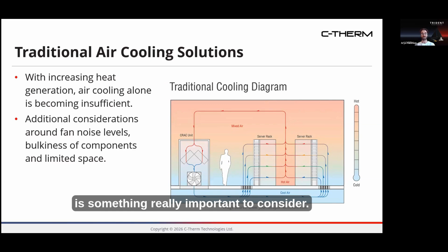You get additional considerations around fan, like the noise level, the overall bulkiness of some of these systems, and of course, the space, because space as a commodity in and of itself is something really important to consider. So of course, we're talking more about the liquid cooling. This specifically, whether it's liquid plate cooling or immersion cooling technologies, these systems by design can vary, but the singular commonality here is that the liquid media, the heat transfer fluid that is used, is going to be a dominating performance factor in how well these systems work.